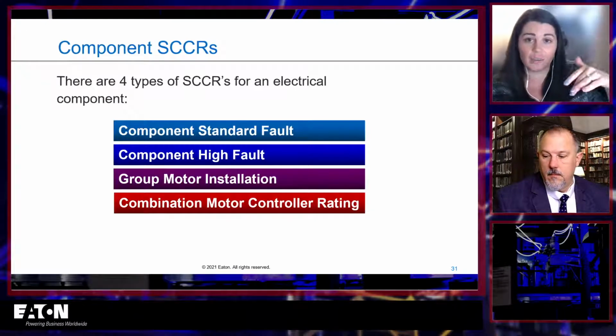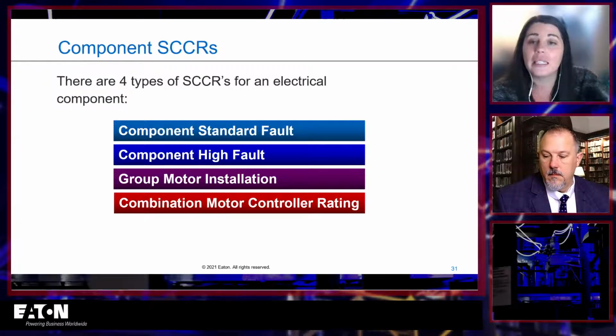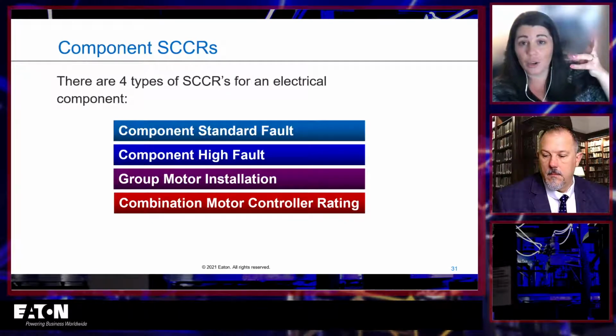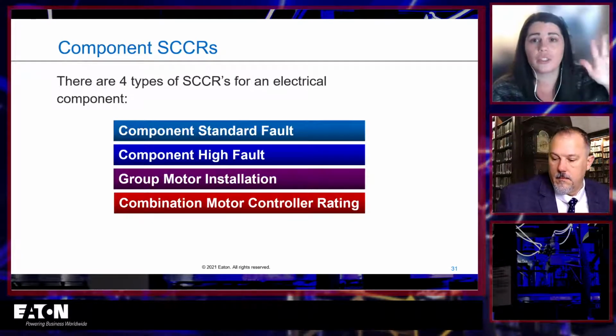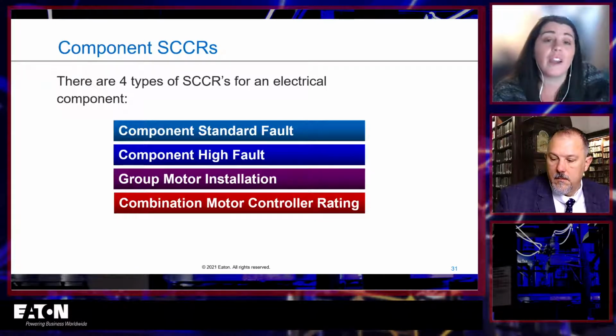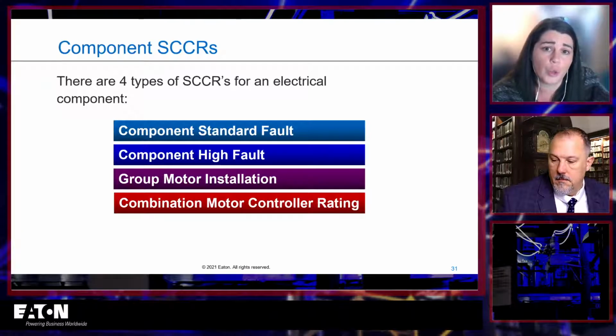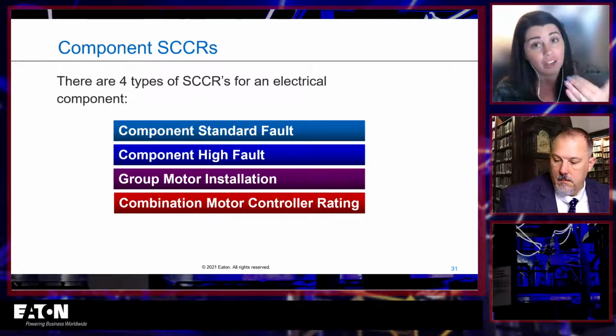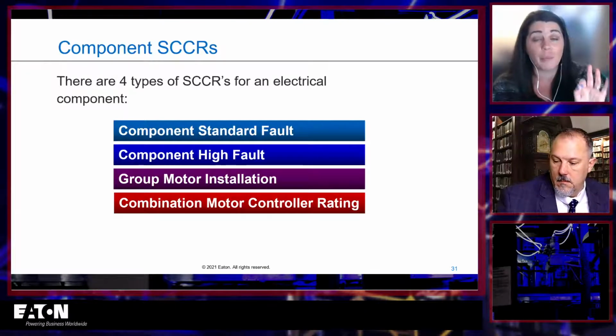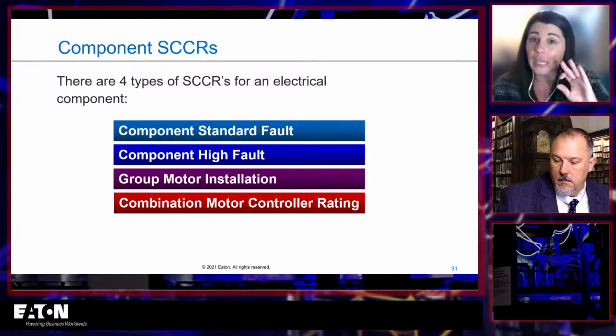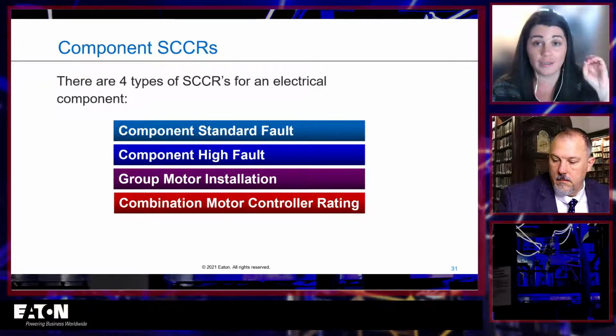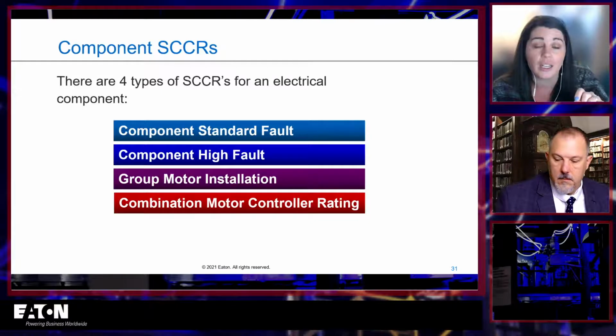So as a result, it might be a different rating because that fuse got a little bit larger, not quite as current limiting, not quite as protective. So it's really important that you have a different rating for it. And then finally, there's a combination motor controller rating. A combination motor controller is a specific combination of components, so this one is part number specific. High fault rating was kind of generic. Combination motor controller rating is the opposite. It is absolutely part number specific.